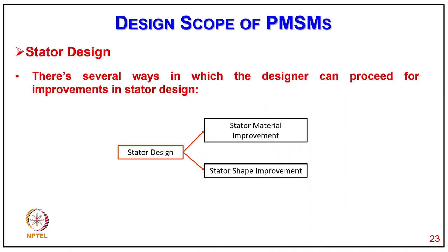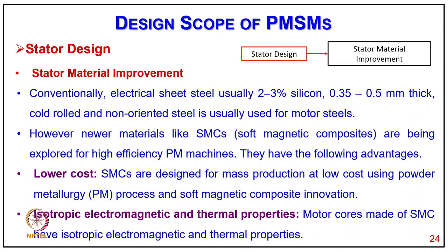Coming to stator design, there are several ways to proceed for improvement: stator material improvement and stator shape improvement. For stator material improvement, conventional electrical steel with 2–3% silicon and 0.35–0.5 mm thickness of cold rolled non-oriented steel is used. However, newer materials like SMC (soft magnetic composites) are explored for high-efficiency permanent magnet machines, offering advantages like lower cost through mass production using powder metallurgy, and isotropic electromagnetic and thermal properties.